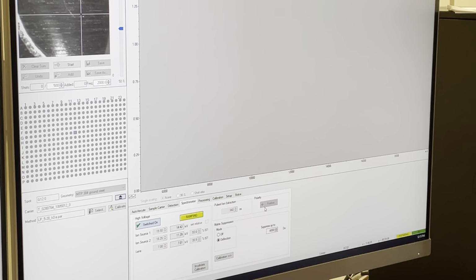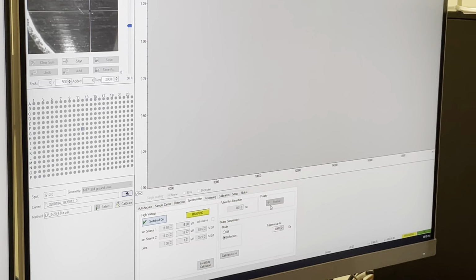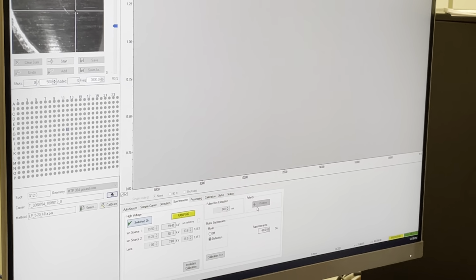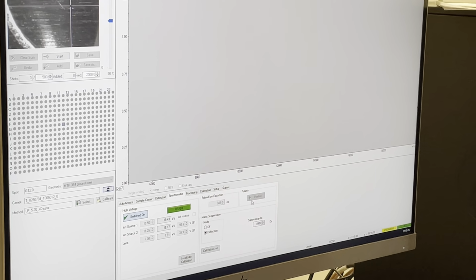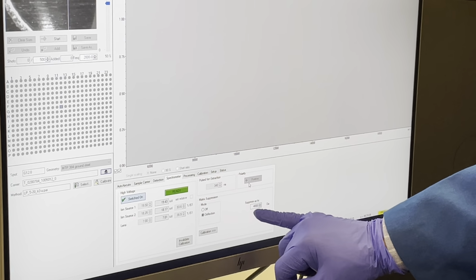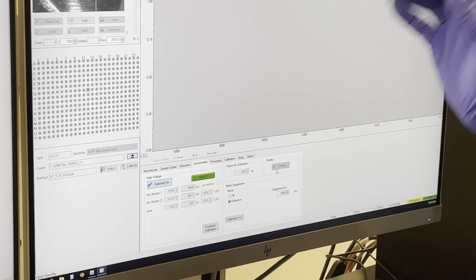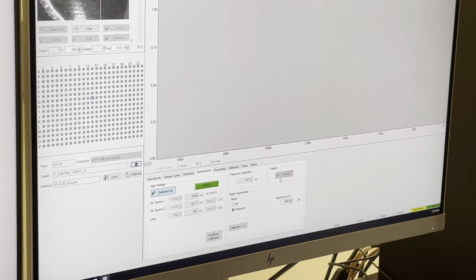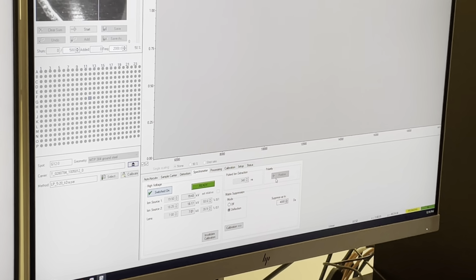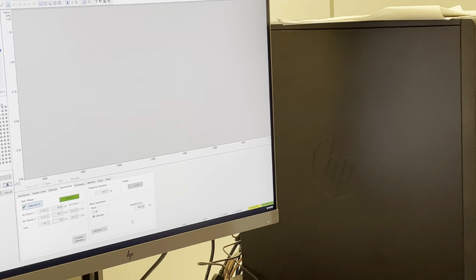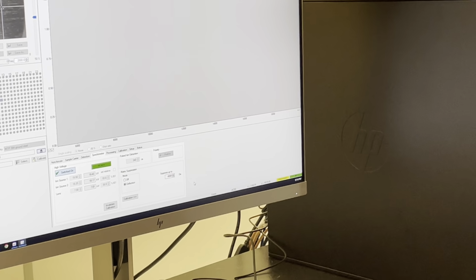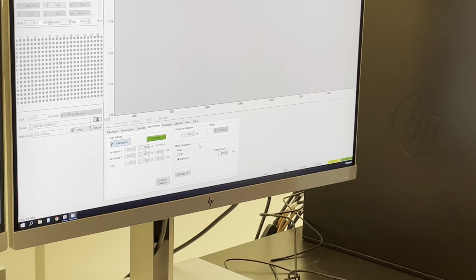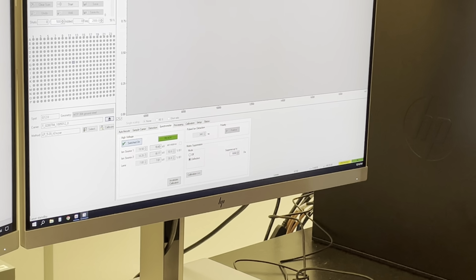Are you interested in anything below 5,000? Right now, no. Okay, that's the reason I asked. Right here we have a setting, deflection, suppress up to 4,000. Anything below 4,000 will be deflected by the electric field, so you cannot see any data for anything below m/z 4,000. Suppose I want to record below 4,000, what do I have to do? Just change the value, but the minimum value is 500. Right here it is 4,000, but we can change it to 5,000 and hit enter. Right now, anything below 5,000 will not be collected by the computer.